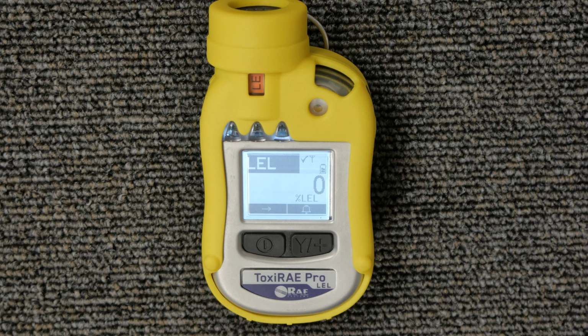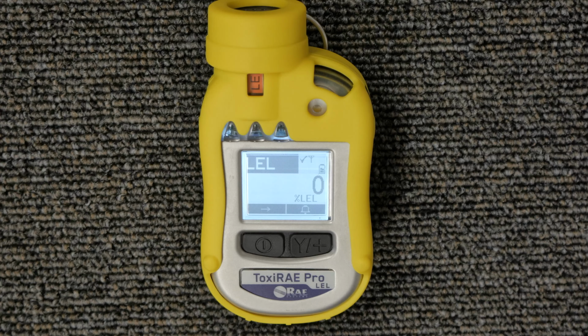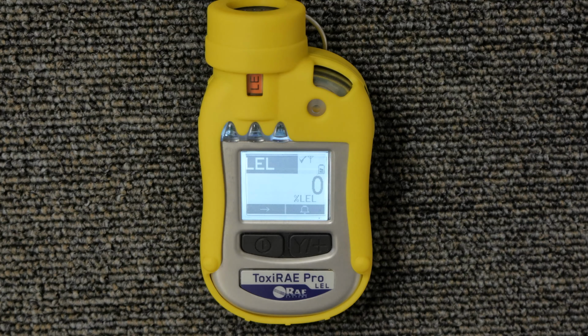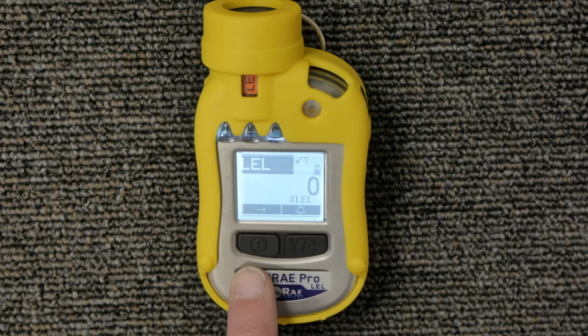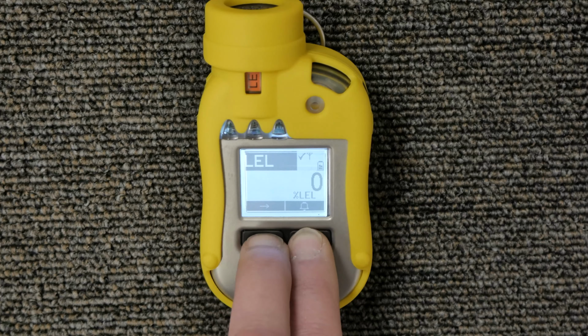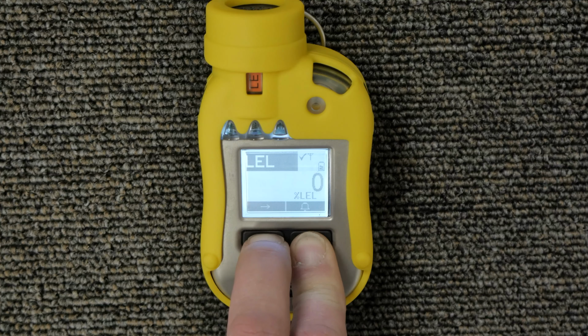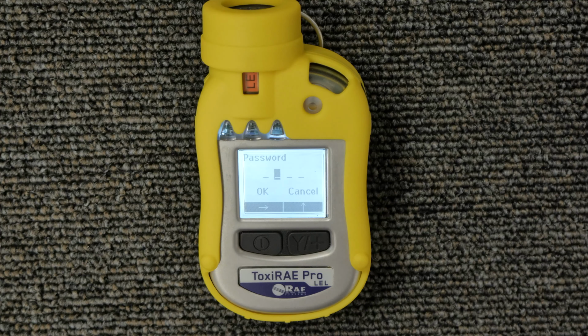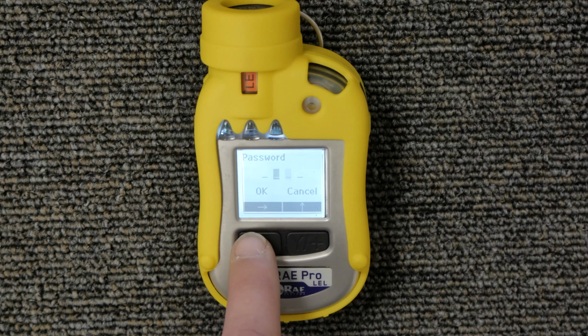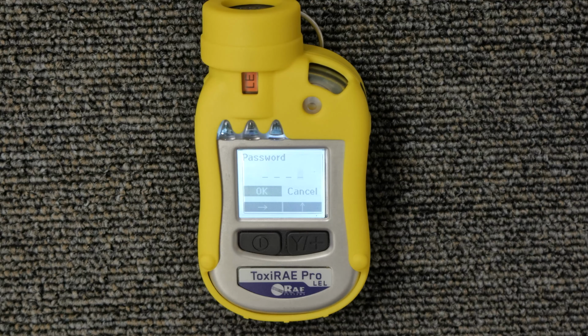Now we're going to do the fresh air calibration on the ToxiRAE Pro. When the unit is in the live reading mode, you want to hold down the power and the Y plus button together at the same time for a couple of seconds. In order to do the fresh air calibration, there is going to be no password. So you can hit the power button to scroll the cursor over until it's over the word OK, then hit the Y plus button to accept that password.